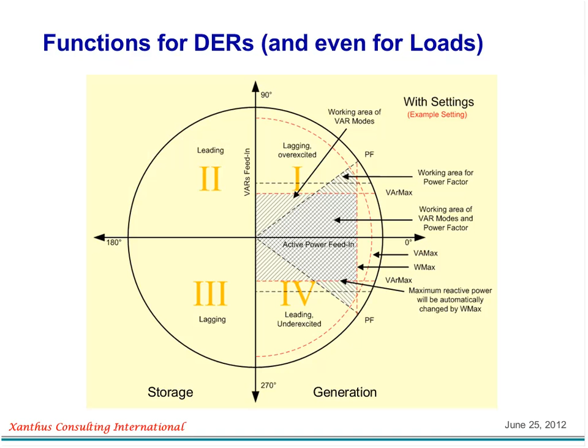So let's take a look at these fancy inverters. They're really 4-quadrant, meaning you can have them move with the VARs leading or lagging, whether they're charging or discharging. That's basically the 4 quadrants. They now use different terms, but I'll leave that to the detailed inverter folks. If you have a generator and storage, particularly a storage device, it actually works in all 4 quadrants. A pure generator can only work in the generator quadrant. So this is what the software can do—it can change those angles and set you in any one of the 4 quadrants if you physically can do that.